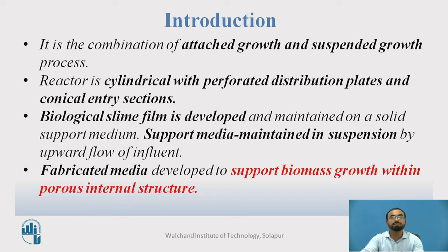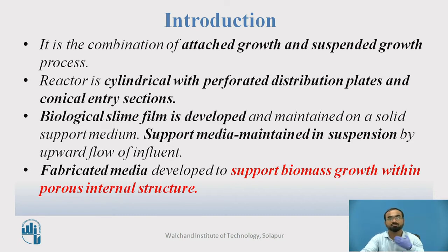A support medium is maintained in suspension by upward flow of influent. The water is flown inside in such a way that the particles acting as a bed for the microorganisms will be continuously in suspension. The water is continuously flown from the bottom upward, so whatever the bioparticles or media present is continuously in suspension. Fabricated media is always developed to support biomass growth within the porous internal structure.